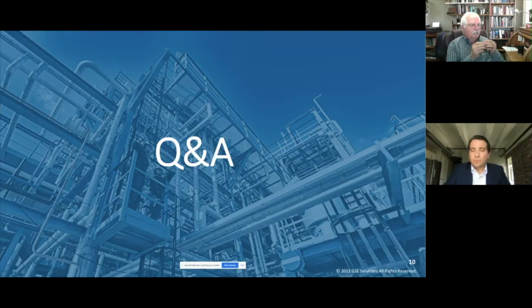But we also were feeding it in through our M&D center overall, which was gathering data on the equipment level, outside of just the thermal performance or DVR type arena. And then what happens there is you see coincidental issues happening. Actually, every morning the site would review the issues identified by the monitoring and diagnostics, which could have been fed through this system or by others, of course. They were assessed on a morning meeting basis, real time, and that was at all of our nuclear units. That was very effective because, of course, not every issue that we identify is a quote unquote real issue. It could have been just something going on unrelated to a failure. But it did help identify failures, which was our goal.